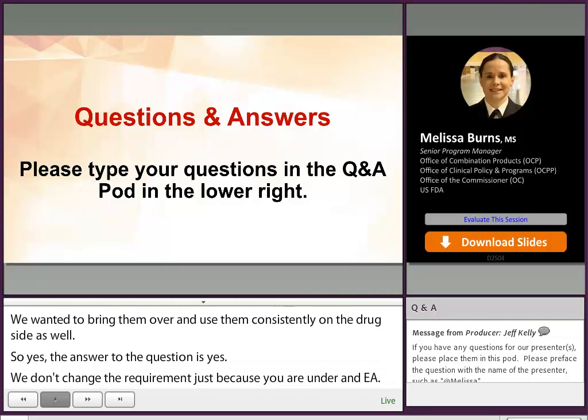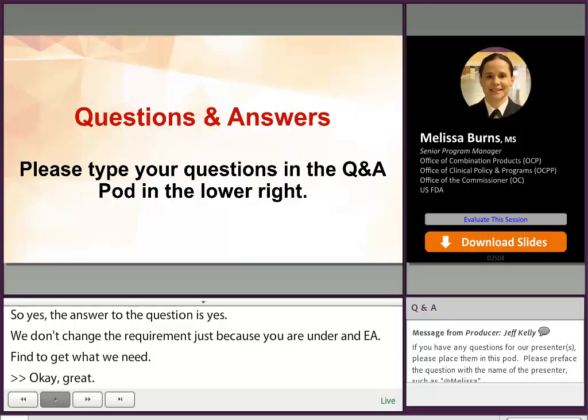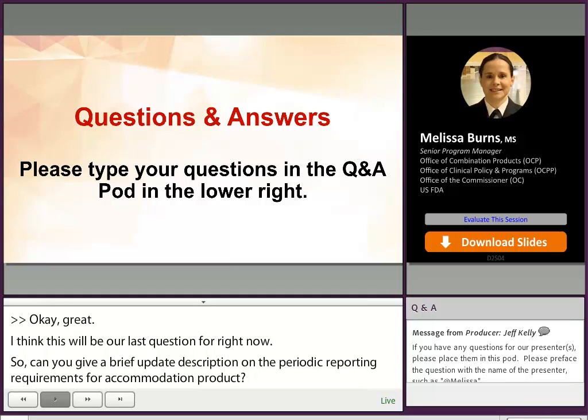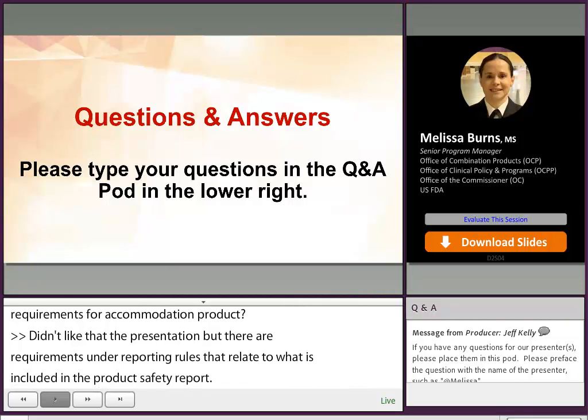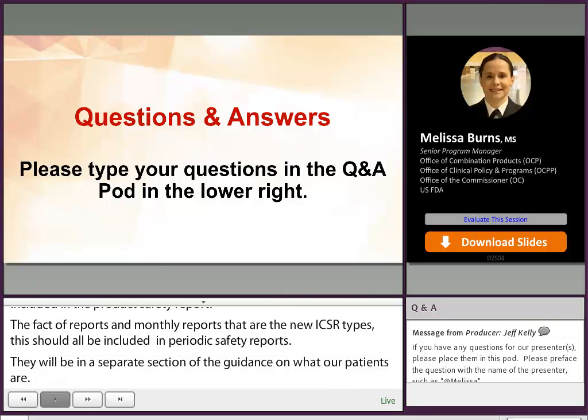Okay, great. And I think this will be our last question for right now. Can you give a brief update or description on the periodic reporting requirements for combination products? Sure. I didn't highlight that in the presentation, but there are also requirements under the Post-Market Safety Reporting rule that relate to what is included in combination product periodic safety reports. The 5-day reports and malfunction reports that are the new ICSR types should also be included in periodic safety reports made to the agency. They'll be in a separate section, and the guidance gives you a little assistance on what our expectations are. But you do have a new obligation to include these individual case safety reports related to malfunctions in 5 days into the periodic reporting that you do for your products.